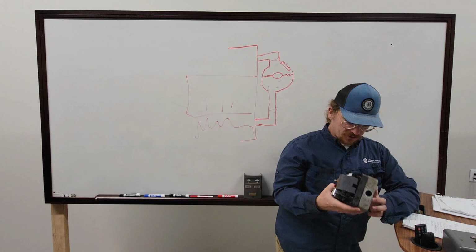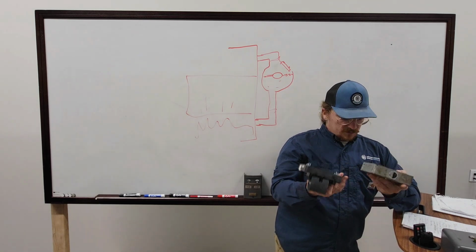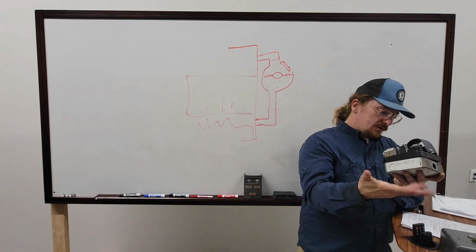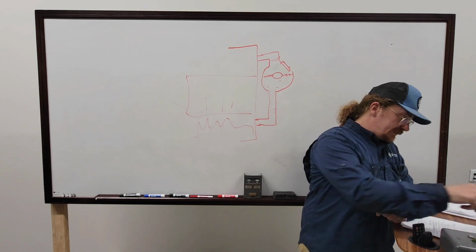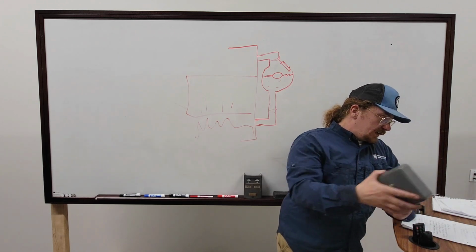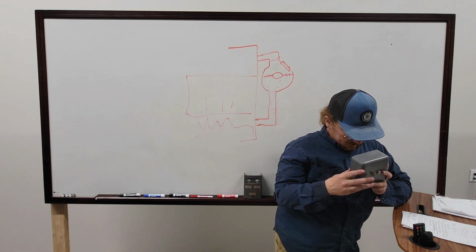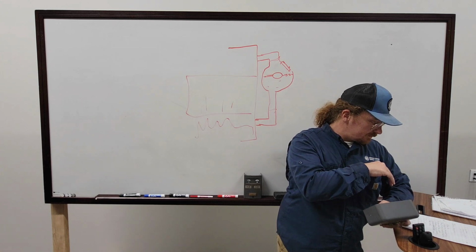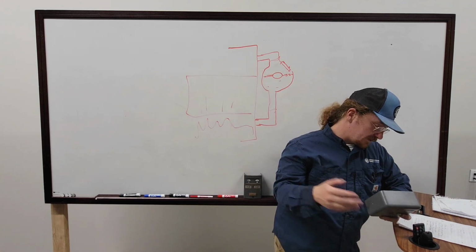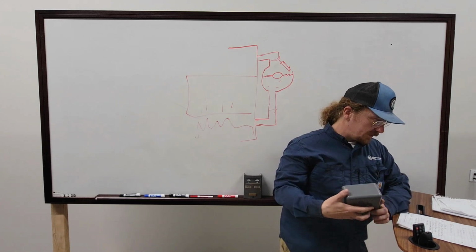It's going to make sure the safeties are met, turn on your gas valve, turn on your pilot valve, and give you an opportunity to test. Interlock all your interlock circuits. Let me make sure I'm not forgetting anything there. Thermostat, UV, your safety. So you're going to establish that flame there. Your limits, pilots, gas, burner, L1, L2.